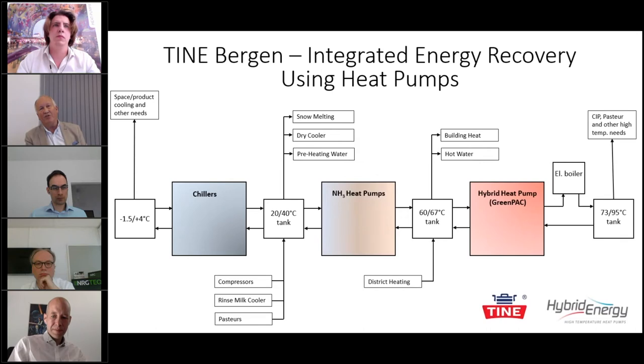When looking at Tine Bergen, it is an integrated energy recovery system using heat pumps. You see that the chillers are still there, and on the warm side you have an electrical boiler serving as a backup unit. In between, you have conventional ammonia operated heat pumps, and the hybrid heat pump that can supply temperatures, in this case, up to 95 degrees Celsius. There are a lot of storage or accumulator tanks at the different temperature levels. It takes care of the same features as in the basic sketch, but you have a complete collection of waste heat and low temperature heat that you can bring up to the correct levels to make it work.